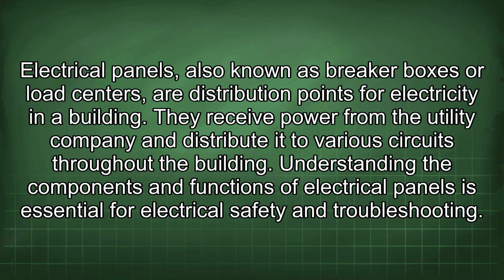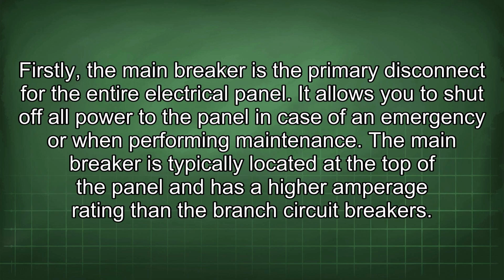Electrical panels, also known as breaker boxes or load centers, are distribution points for electricity in a building. They receive power from the utility company and distribute it to various circuits throughout the building. Understanding the components and functions of electrical panels is essential for electrical safety and troubleshooting. Firstly, the main breaker is the primary disconnect for the entire electrical panel. It allows you to shut off all power to the panel in case of an emergency or when performing maintenance.